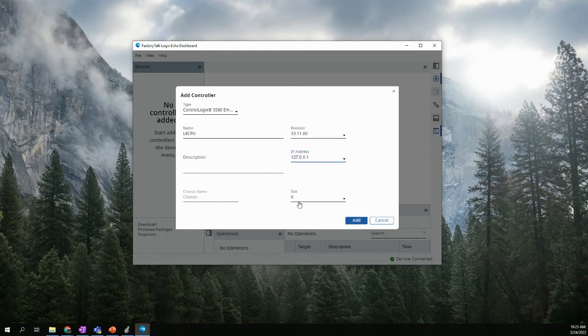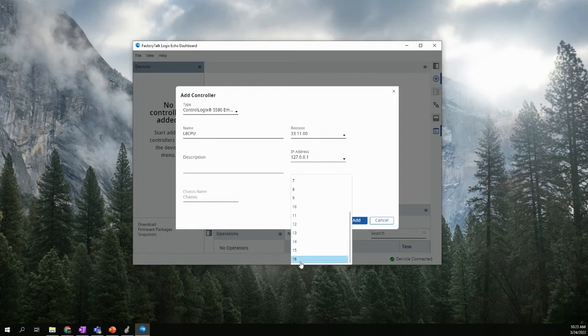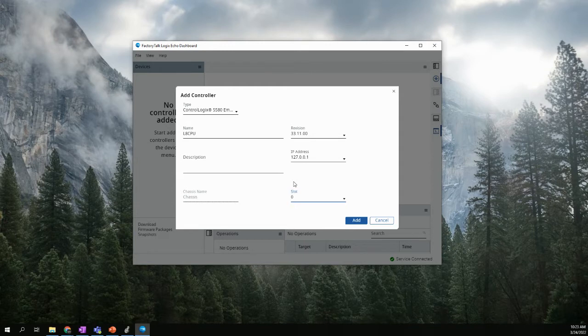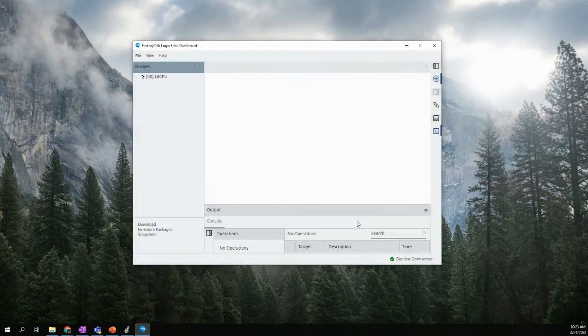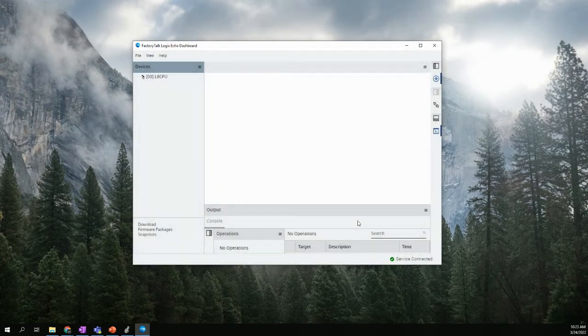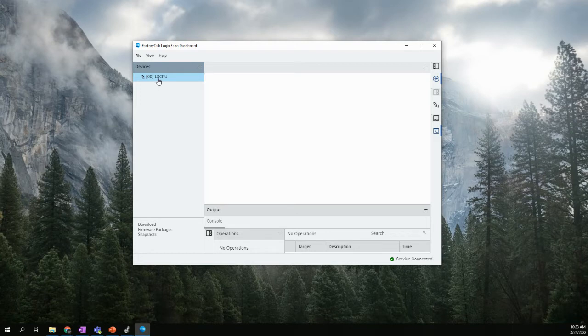And slot. This will basically be what slot in this virtual chassis do we want to put the CPU in. I would recommend keeping it in slot 0. But you can pick anywhere from 0 to slot 16, because you can actually have multiple emulated CPUs in this Logix Echo chassis. We'll keep it on slot 0, and we'll say add. So now this bracket 00 indicates that it is in slot 0, and that's the name of my CPU, L8 CPU.